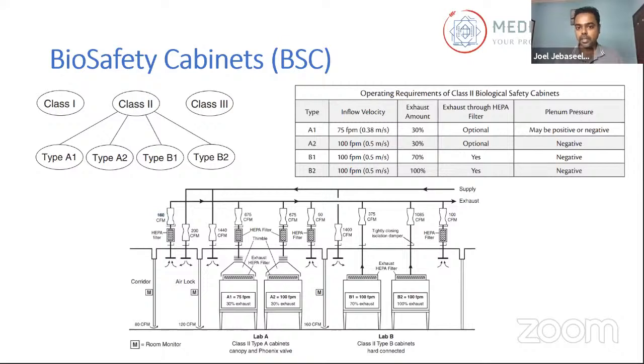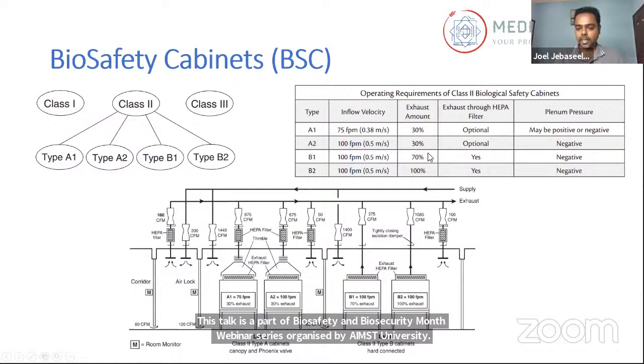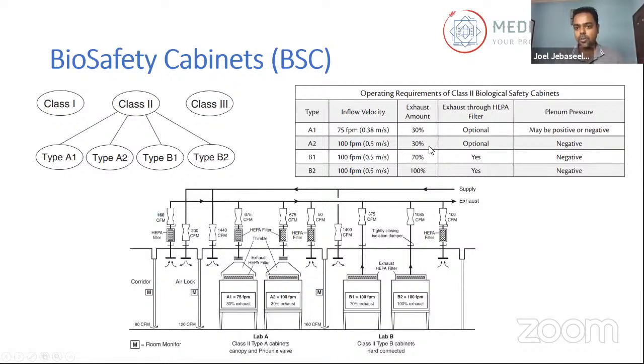And also, for example, if you look at the exhaust from the biosafety cabinets, in A1 and A2, only 30% of the air that goes out of the cabinet is exhausted out. The remaining 70% gets recirculated within the cabinet and doesn't go into the room. But if you look at the most stringent type of class 2, the B2 cabinet, 100% of the air is exhausted out. It goes through HEPA filters and sometimes double HEPA filters before it's safely discharged to the environment.